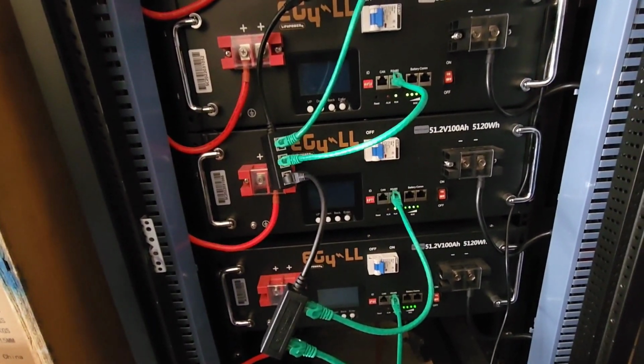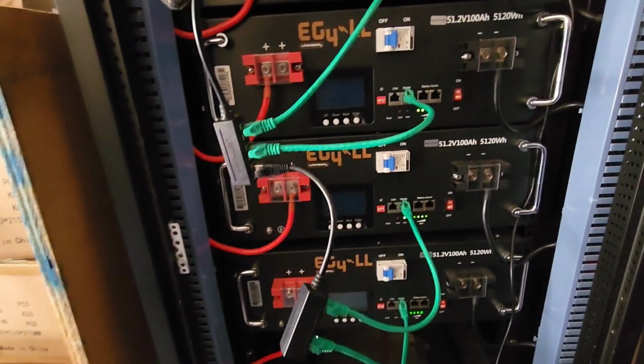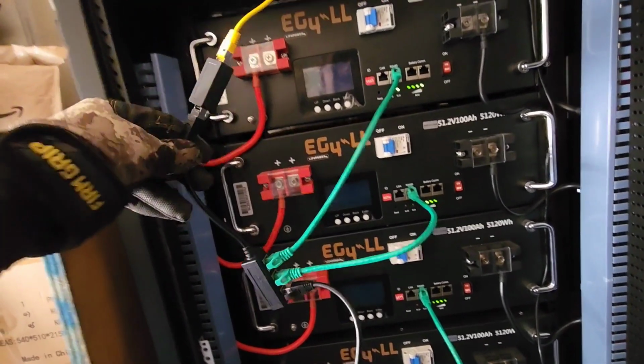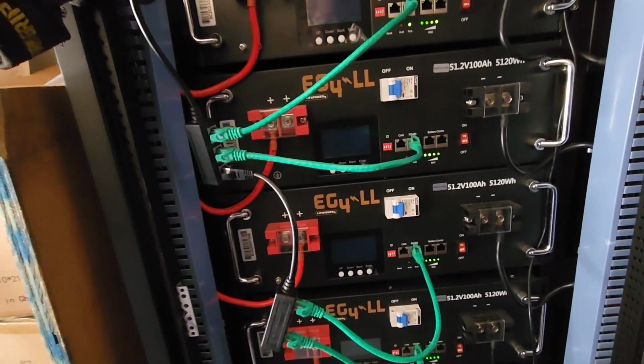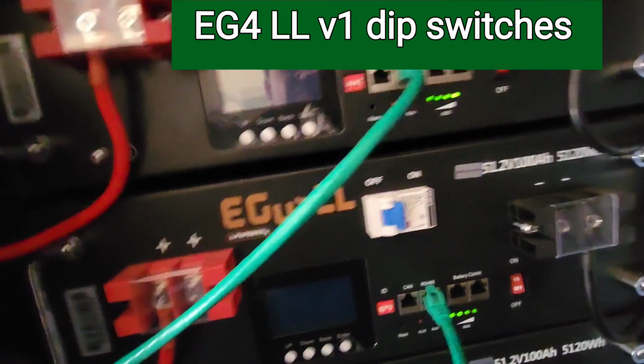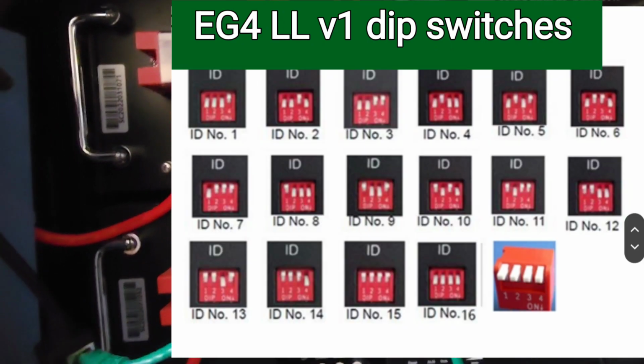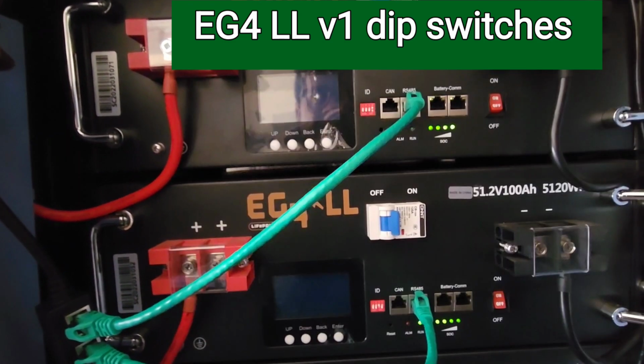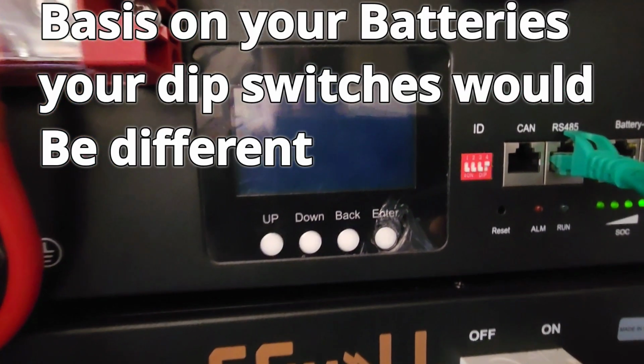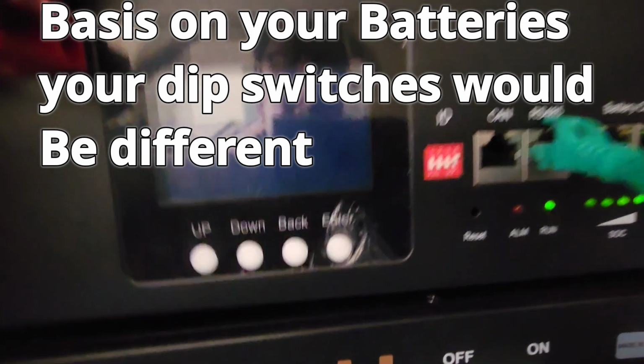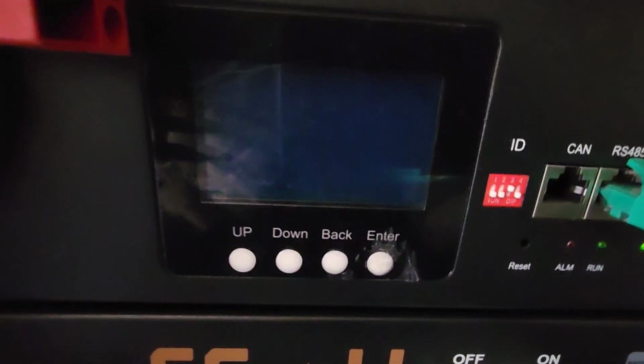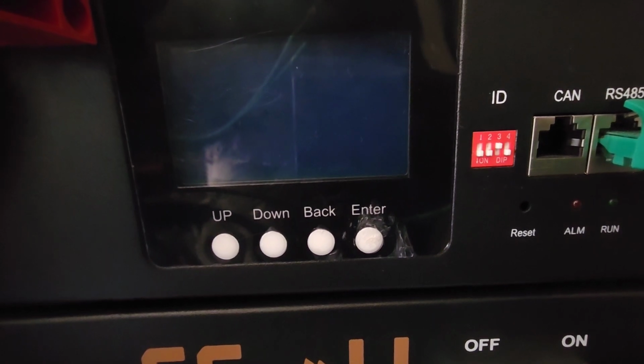So once you've got all this connected with your dip switches, with the splitter from each battery, from each battery we've got everything connected. Now you have to make sure your dip switches are in the right position. Your master battery, which is number one, the dip switches are supposed to be down, down, down, up. The second battery, dip switches down, down, up, down.